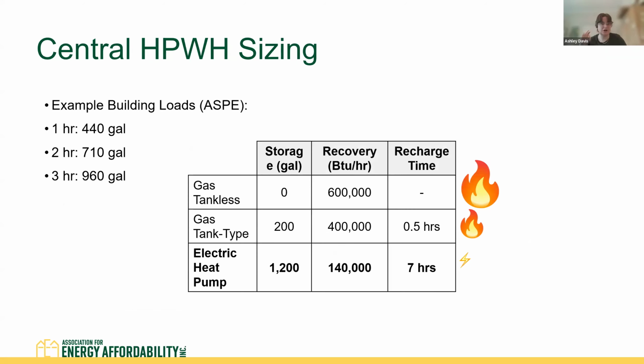So again, just the example that Ari mentioned earlier, looking at a building with loads calculated based on ASPE standards, you can see that the heat pump plant is going to have significantly more storage, but significantly less primary heating capacity compared to either gas configuration, which is going to mean that your recharge time is longer. Next slide.